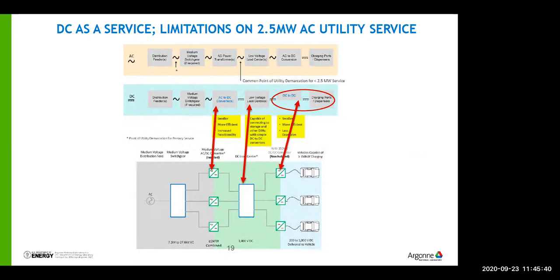The top row shows the AC solution using medium voltage down to low voltage. You have your distribution feeder at medium voltage, those blue power lines we saw earlier. The medium voltage switchgear isn't small, it takes up the size of a car parking spot. Then the transformer can take up the size of another light-duty vehicle, a sedan. That big brick of steel and oil takes up space. And then we get to the 480 volt, 2.5 megawatt service.